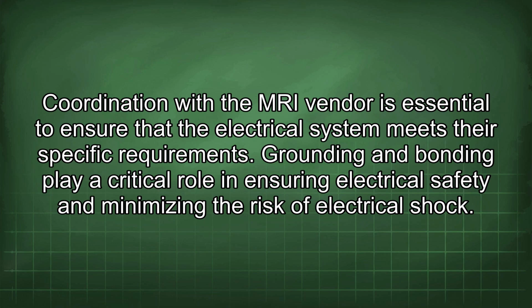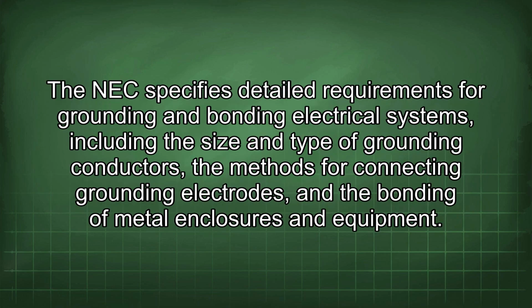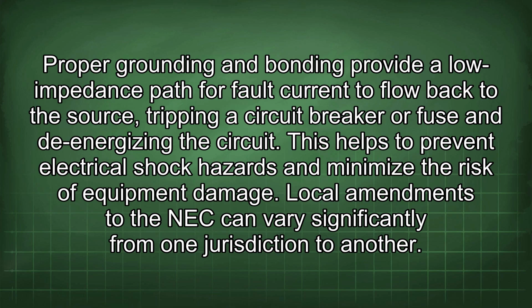Grounding and bonding play a critical role in ensuring electrical safety and minimizing the risk of electrical shock. The NEC specifies detailed requirements for grounding and bonding electrical systems, including the size and type of grounding conductors, the methods for connecting grounding electrodes, and the bonding of metal enclosures and equipment. Proper grounding and bonding provide a lower impedance path for fault current to flow back to the source, tripping a circuit breaker or fuse and de-energizing the circuit. This helps to prevent electrical shock hazards and minimize the risk of equipment damage.